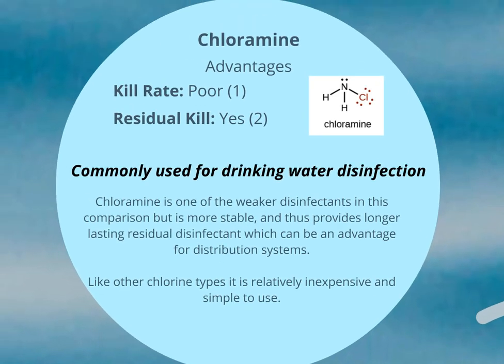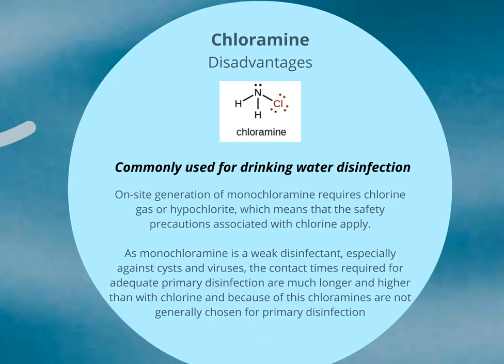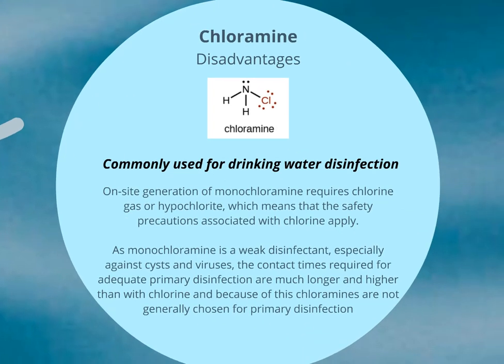Chloramine has a poorer kill rate than other disinfectants. It does have residual kill, so it's still used in drinking water disinfection. It's weaker than other disinfectants in this comparison, but because of its stability it provides a longer-lasting residual disinfectant, which can be an advantage for distribution systems. Like other chlorine types it's relatively inexpensive and simple to use. However, on-site generation requires chlorine gas or hypochlorite, meaning the safety precautions associated with chlorine apply. As it's a weaker disinfectant, especially against cysts and viruses, the contact time required for adequate primary disinfection is much longer, so chloramines are not generally chosen as a primary disinfectant.